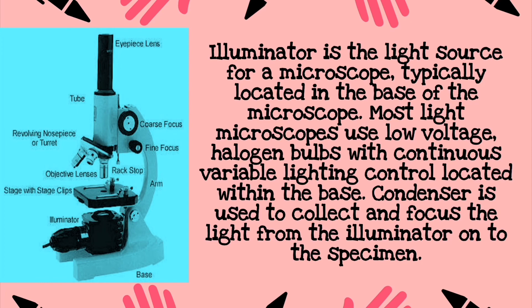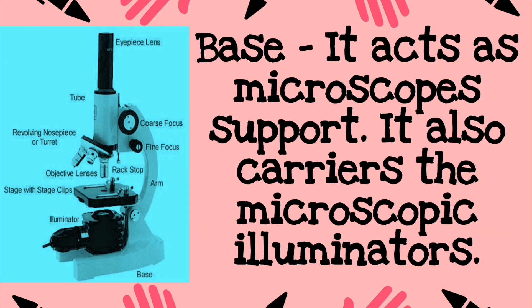Next is the illuminator, the light source for a microscope, typically located in the base. Most light microscopes use low-voltage halogen bulbs with continuous variable lighting control located within the base. The condenser is used to collect and focus the light from the illuminator onto the specimen.